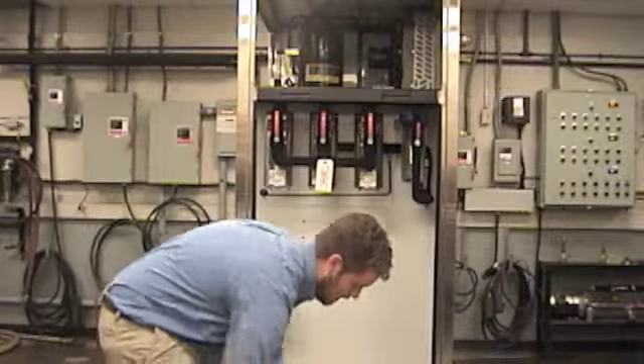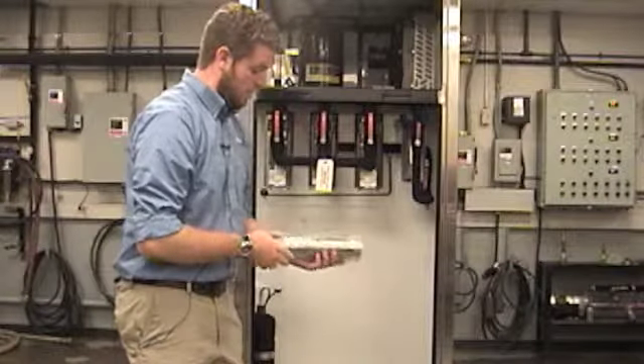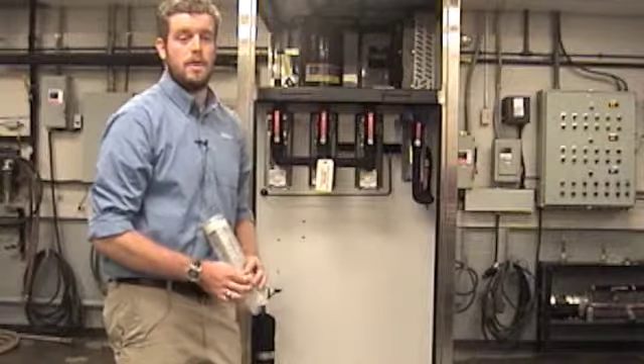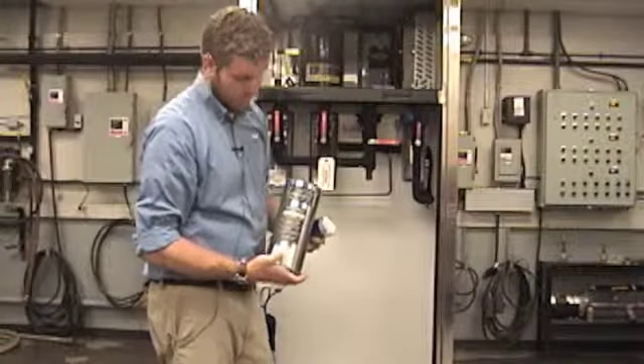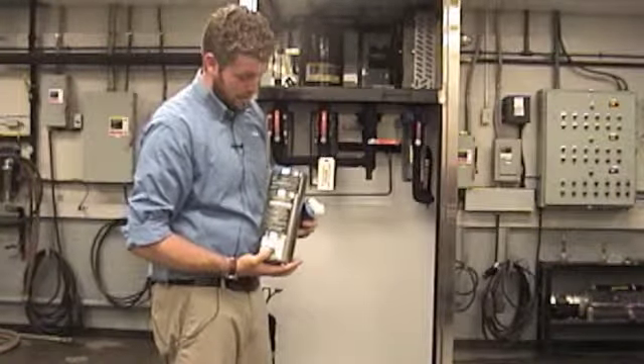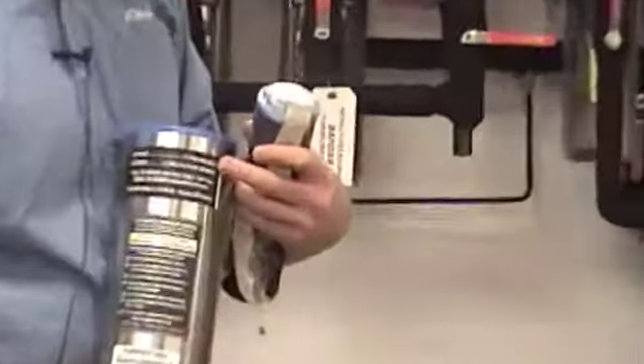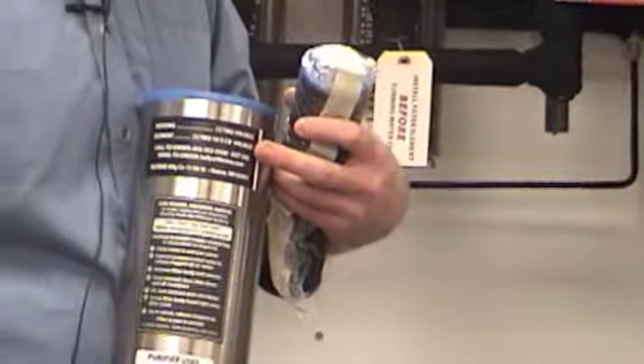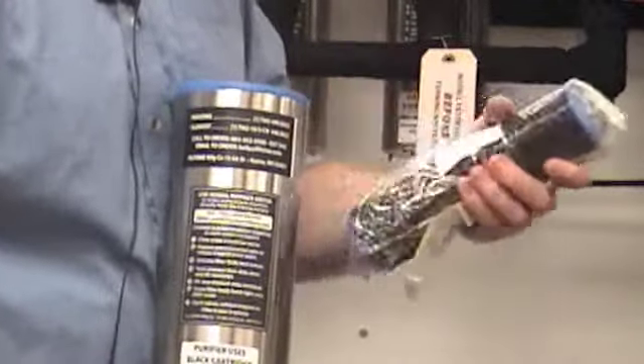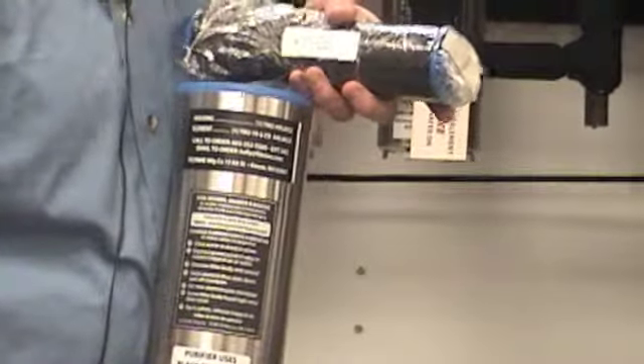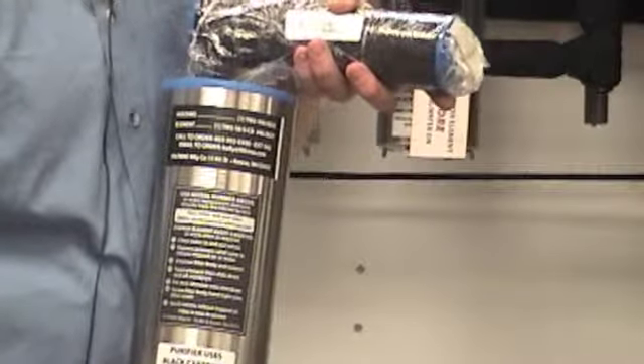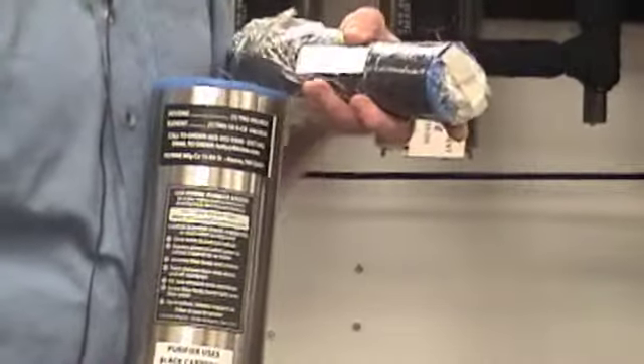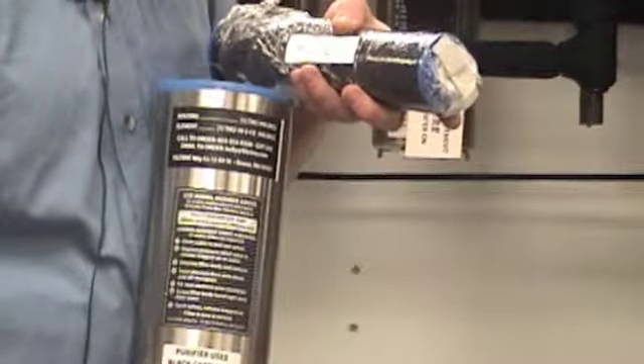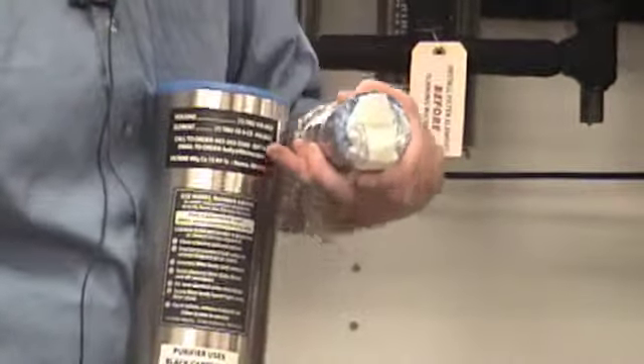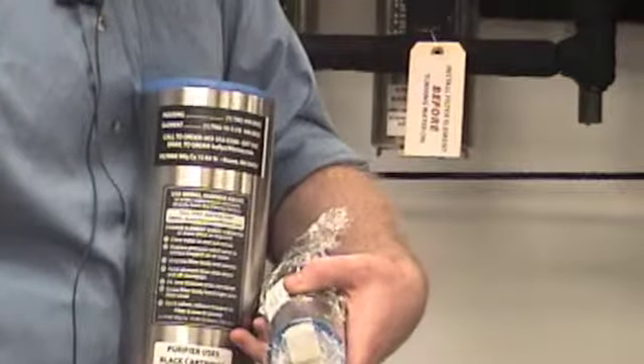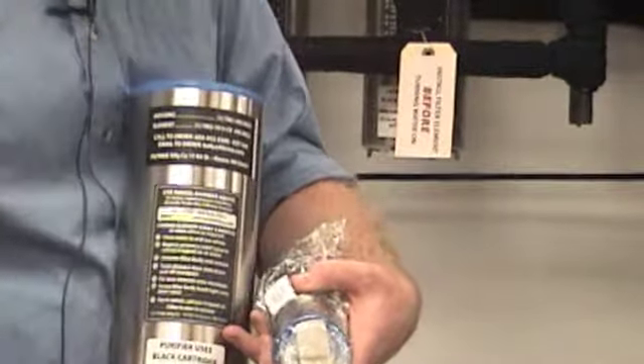Inside this box, you'll have a year's worth of elements. So we recommend changing the elements out 3 times a year. Each housing will have various information on it. It'll give you the housing type, the element number for reordering, and also it's a good idea to match the sticker on the spare element with the housing itself to make sure you get them in the right spot. It'll also give you our information for reorder, and it'll give you a description of changing a filter, basically what we're doing right now.